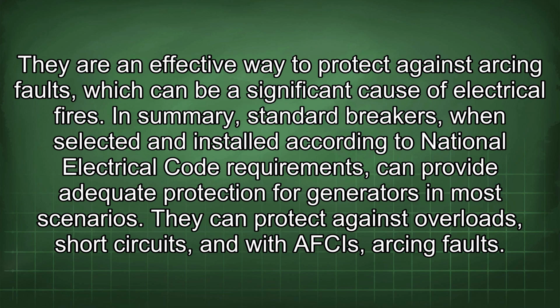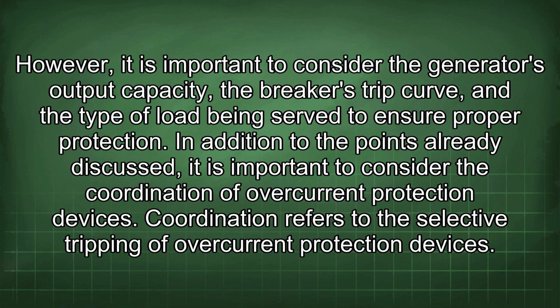In summary, standard breakers, when selected and installed according to National Electrical Code requirements, can provide adequate protection for generators in most scenarios. They can protect against overloads, short circuits, and with AFCIs, arcing faults. However, it is important to consider the generator's output capacity, the breaker's trip curve, and the type of load being served to ensure proper protection.